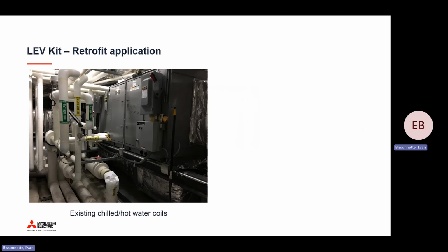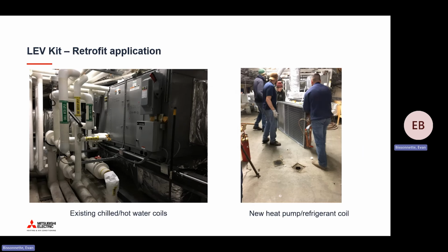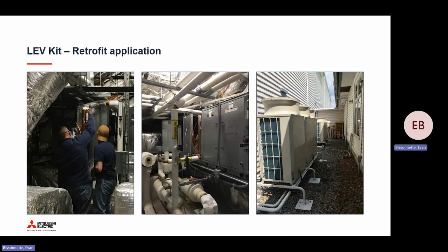So what does that look like? Here you can see an example of an existing air handling unit that was fed by hot and chilled water coils. So we selected a new heat pump coil, selected it so that it fit inside the existing opening of that unit, and met all of the capacities and CFMs that are required. Piped it to our condensing units using that LEV kit that I mentioned, and run the refrigerant piping out to wherever the condensing units need to be located, whether that be right on the roof with the unit or hundreds of feet away if needed.